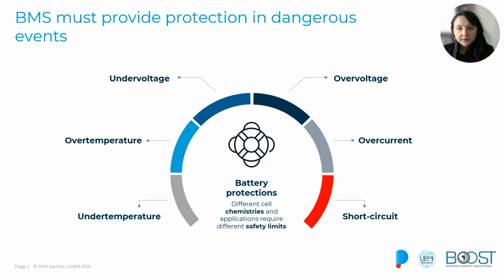The most relevant dangerous events that require protections are going to be related to the parameters that we have been exploring in the previous slides, like the current, the temperature, the voltage, and the loss of insulation. Different cell chemistries and different applications will require different safety limits for these parameters, but in general, we need to have protections for any of these events that include, for instance, over temperature, under voltage, over voltage, over current, and short circuit. We will explain each of those in the next slides.